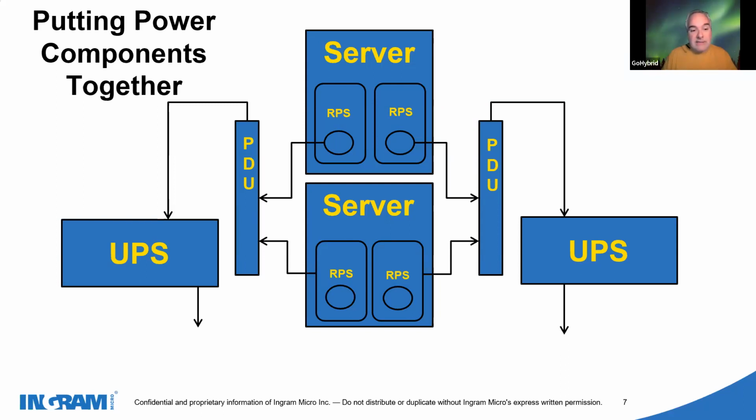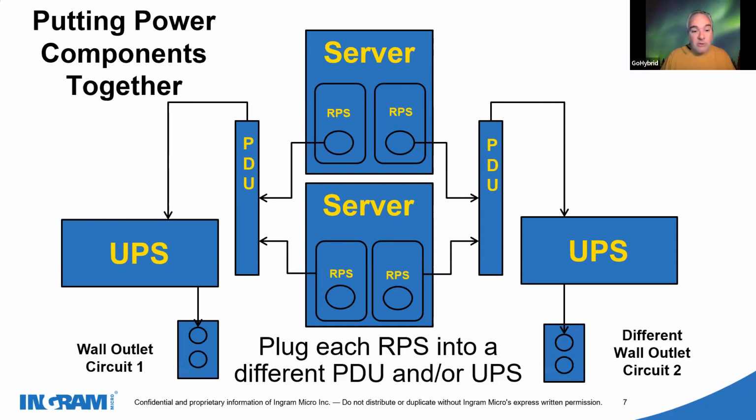With this example, I have half of the power supplies in each data center product, my servers, my storage, my networking, attached to different PDUs going to a different UPS. And then finally, you want to make sure those UPSs are plugged into different circuits in your data center.